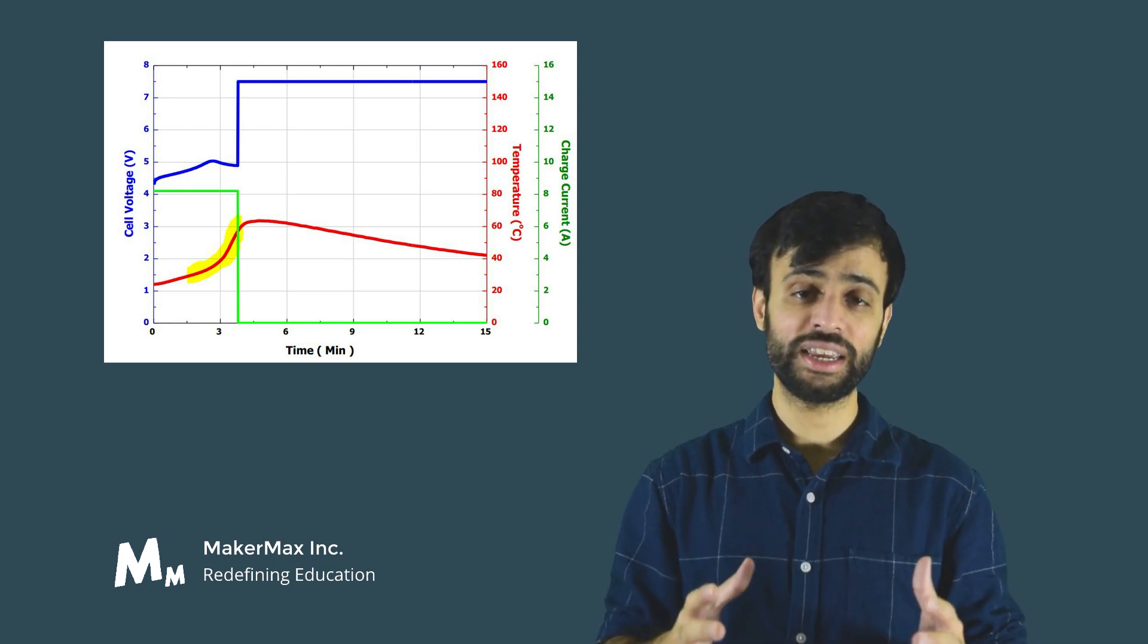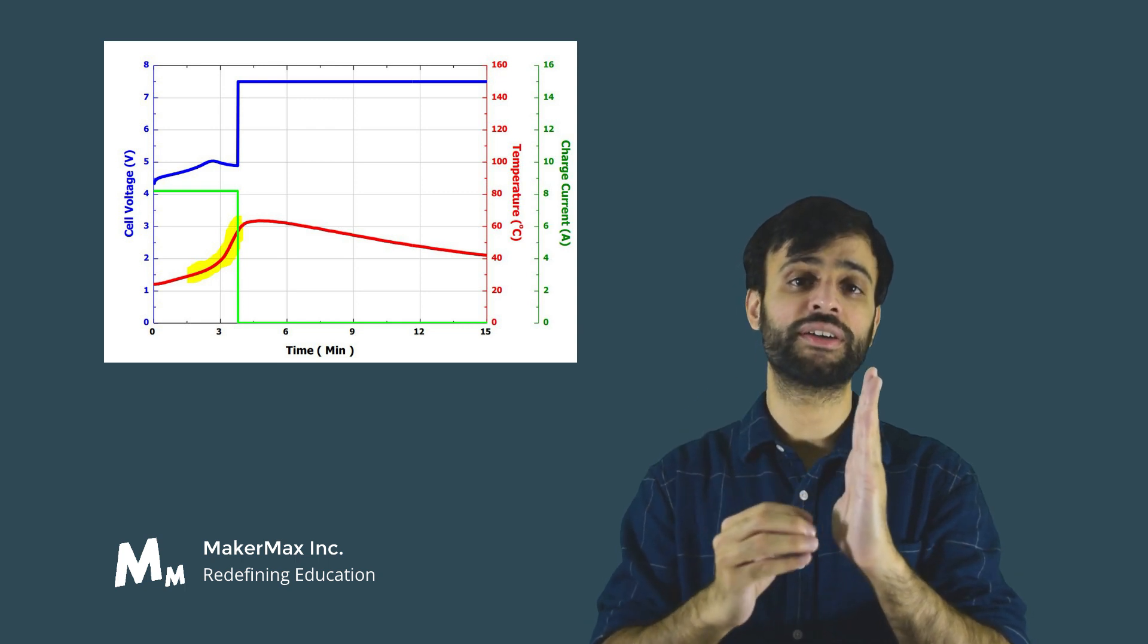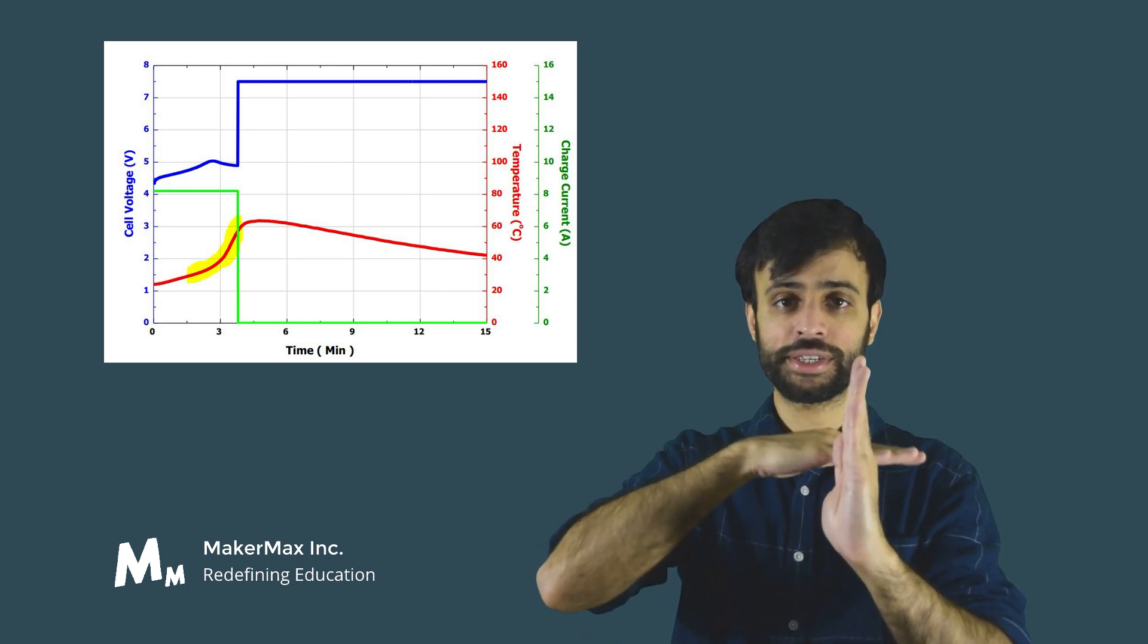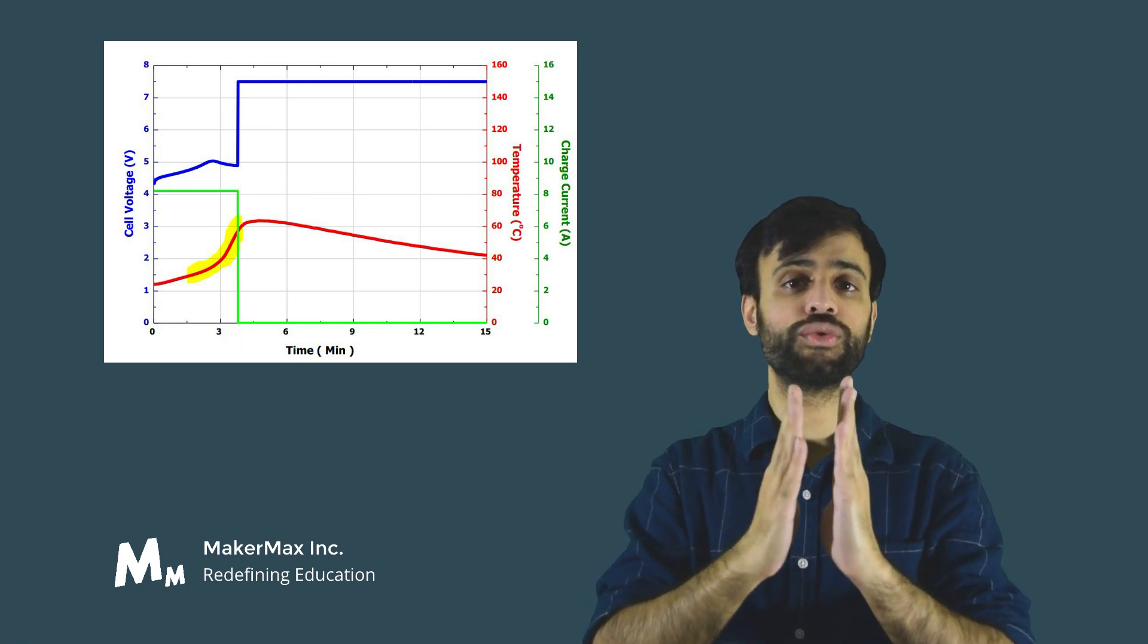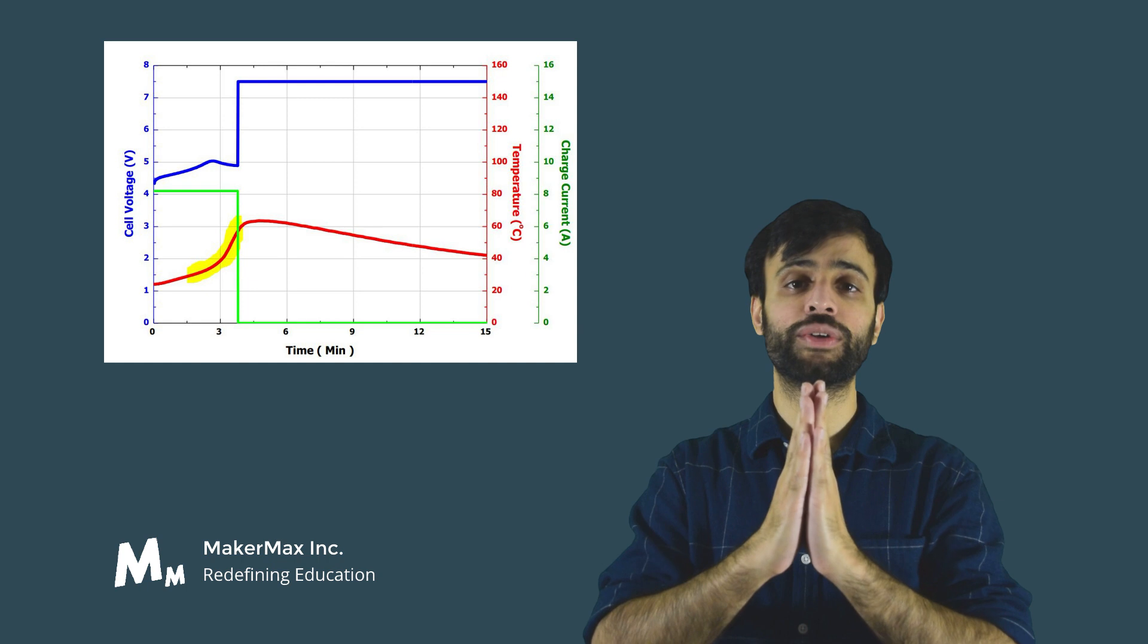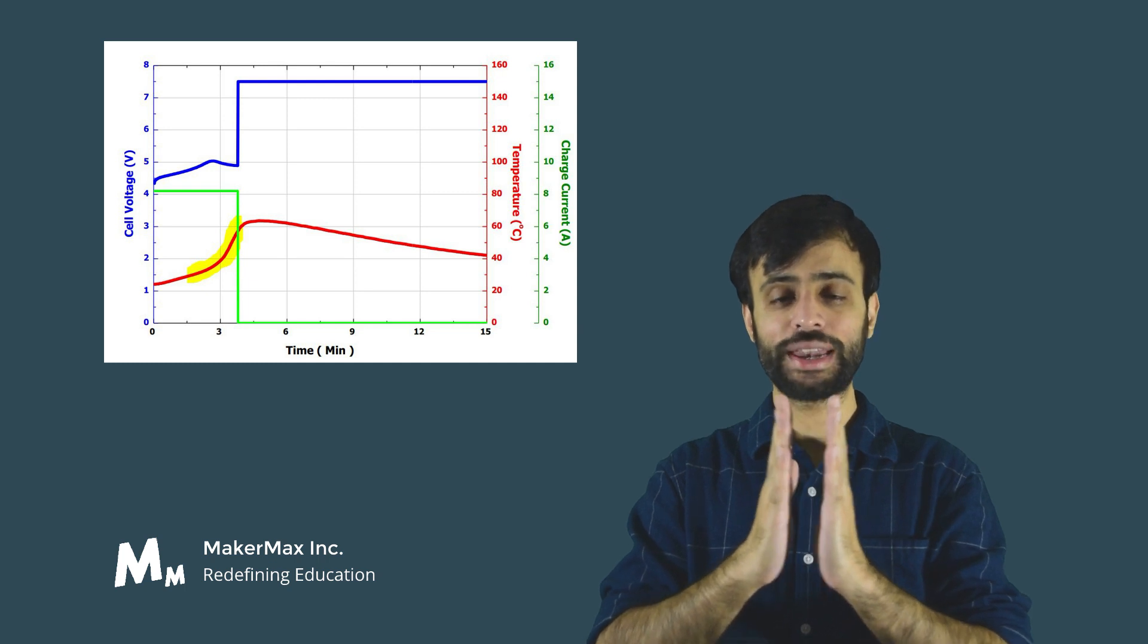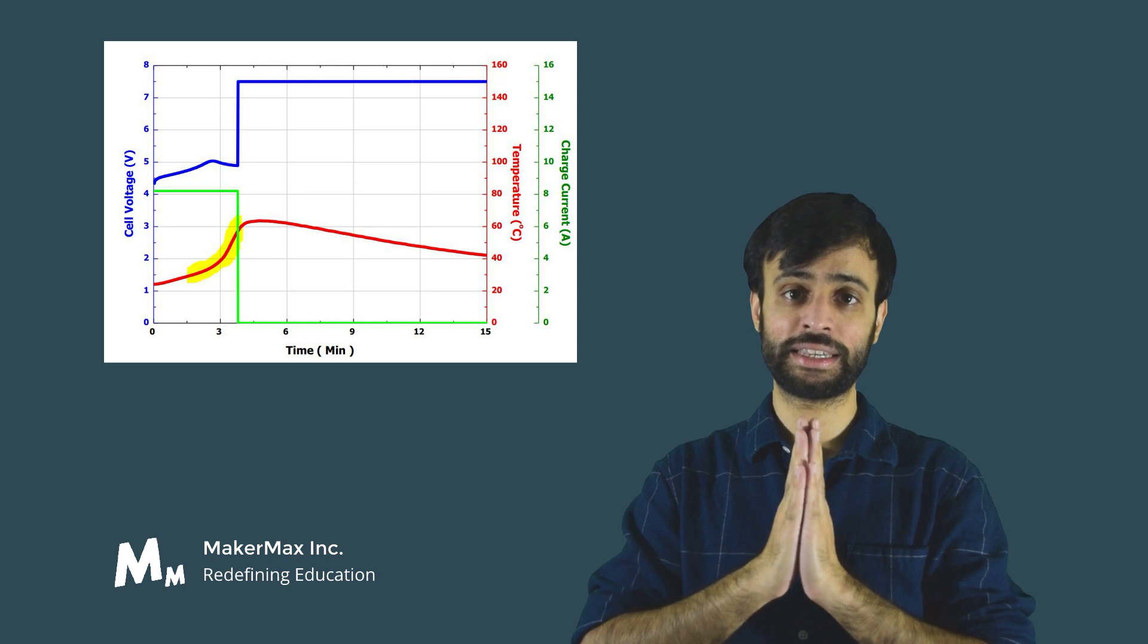This will cause stage two of thermal runaway. In stage two, there are further chemical reactions catalyzed that wouldn't have happened in stage one. Because the temperature has crossed the stage one threshold and reached stage two, the stage two reactions start to catalyze and happen, generating even more heat and rising the pressure inside the cell, creating a high temperature, high pressure environment.